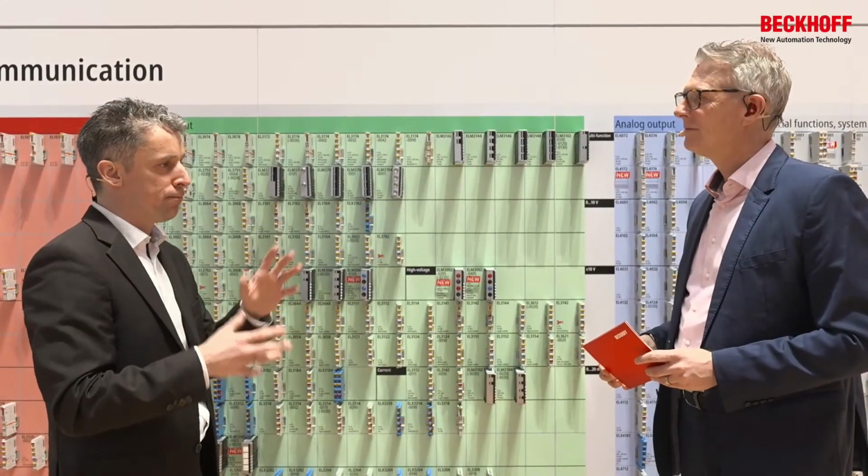And obviously, we also want to serve our customers with more or less everything they need for an energy application, and then they need current transformers. They get them from us from 1 amp up to 5,000 amps, also in different accuracy classes. Maybe class 3 is enough, but maybe you want to be very precise and go for 0.5. Or maybe you have an old application you want to retrofit, then you need split core devices, because the primary conductor should not be opened again, so the transformer needs to be opened. No problem, we have them in two different versions, in big and small.